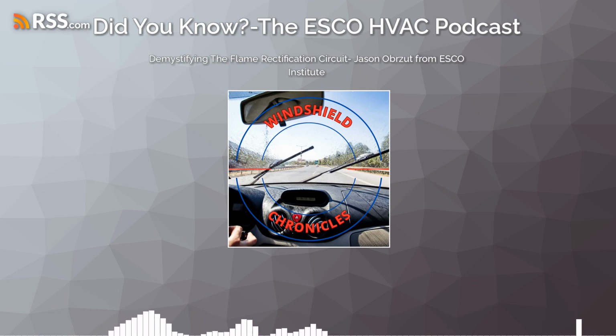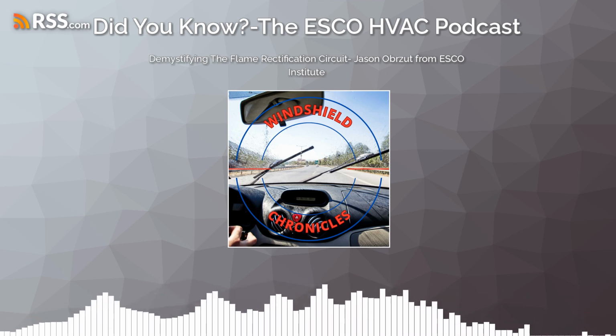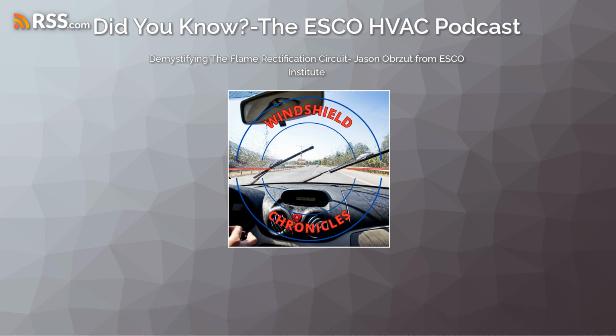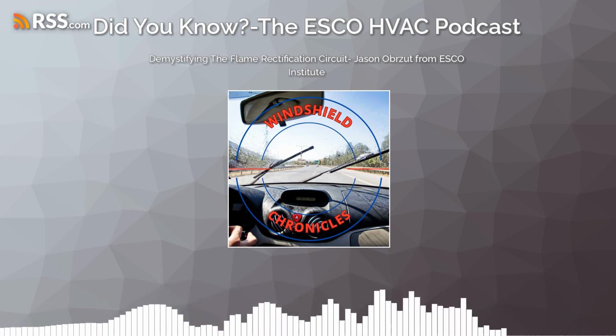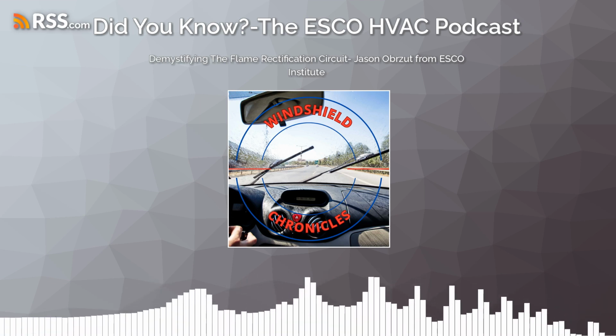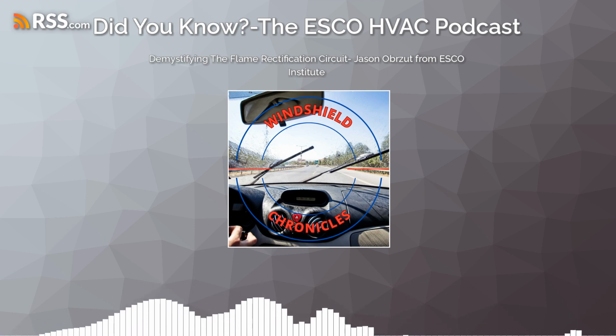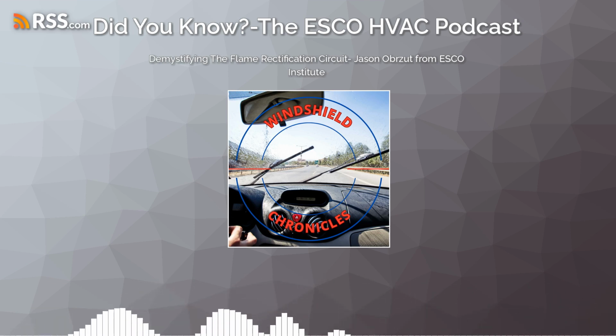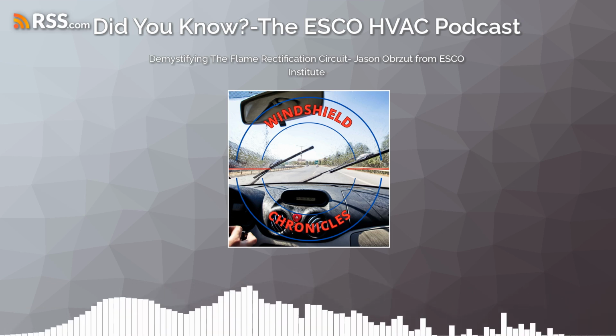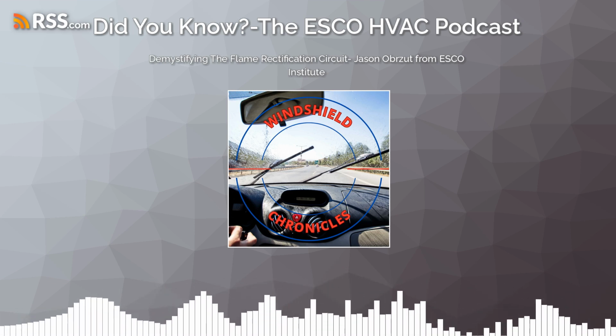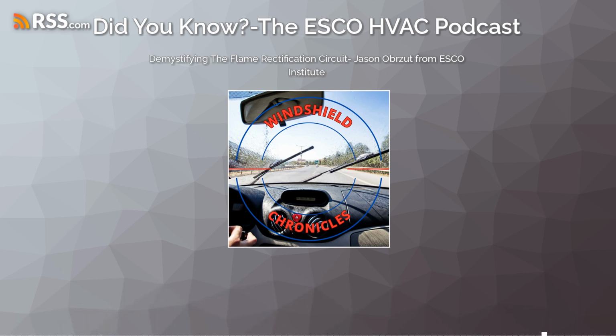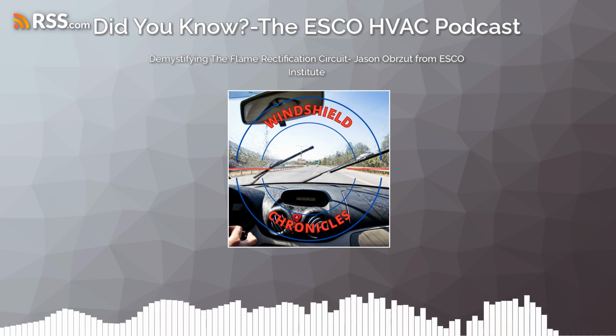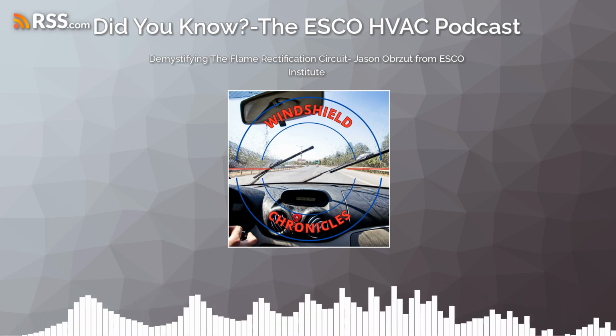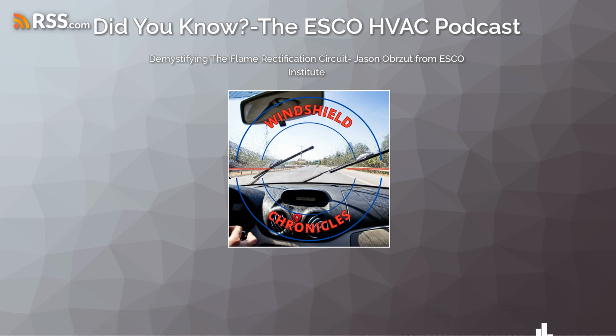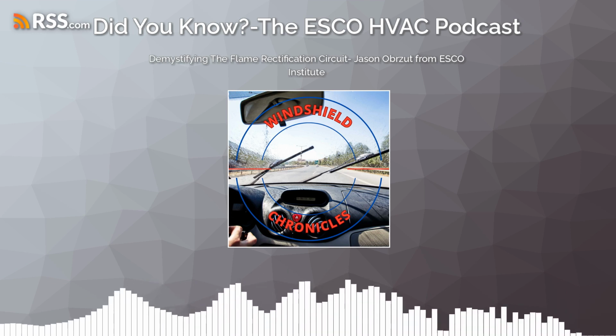Okay. So that's step one, to be able to see what we're doing. So we're going to apply AC voltage back onto that wiring diagram. Let's go over that wiring diagram and let's complete this path. So what we're going to do on that flame rod, we apply AC voltage. That AC voltage comes out of our board and it's going to go to the rod. It's going to pass through the flame back onto that dedicated ground wire. And it is such a dedicated ground wire that if we look at this separate burner assembly that I have here, Jason, this is something that we can never overlook on a gas furnace, right? Our dedicated ground wire from that control board lands on the burner box so that we can get as close of a connection to our burners as possible.